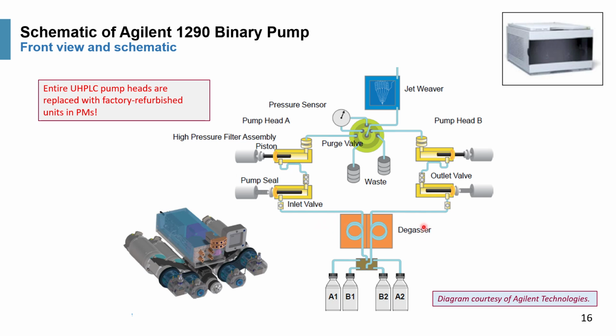This pump is a dual piston in series, so since each of the pumps would have 2 pistons, right? A low pressure piston and then a high pressure piston in there, and they're actually being driven with a digital motor in here. So both, and it shows you the actual inlet check valve and the outlet check valve, right? So this is the schematic of the 1290.